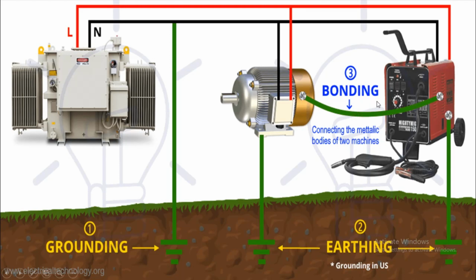Bonding means connections between two pieces of equipment by the green cables connecting the metallic bodies of two machines. Okay, so that is the bonding. But of course, both of this equipment should be earthed in their body with the earthing cables connected to the ground. Okay, so that is the diagram for the grounding and earthing. So there is no big difference between earthing and grounding. It's the same, only the terminology, because earthing is British and grounding is US, but it's the same.